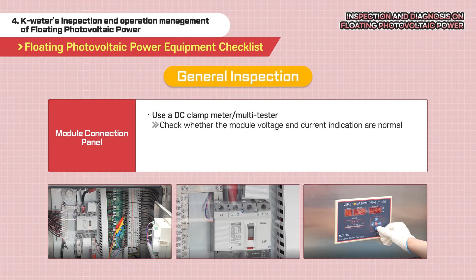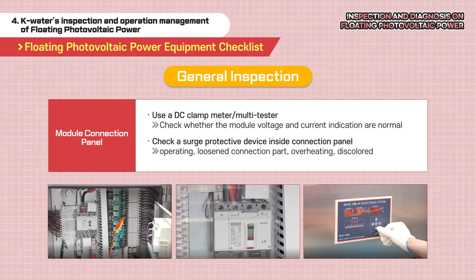Surge protective devices are generally installed inside the connection panel. During an inspection, it is possible to check whether an abnormal voltage has occurred in the equipment inside the connection panel by determining whether the counter of the surge protector is operating or not.